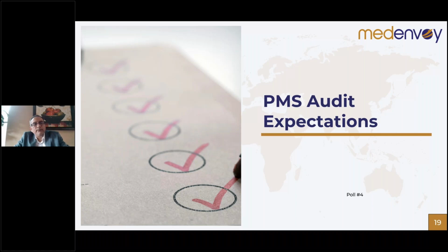So even if your device is established technology and there's no outstanding residual risk, you still need a post-market clinical follow-up plan. You must have a plan covering all the elements as required by the MDR. Then within that plan, you can justify if you need to conduct any activity or not. You can link back with your risk management. You can still demonstrate that it's part of the continuous post-market surveillance regime, but we cannot accept as an auditing organization that you don't have a PMCF plan and activity. So it must be defined and documented, and even though there is no ongoing activity, you must have a plan and documented rationale for what the status is.